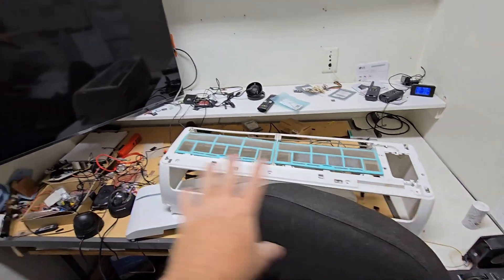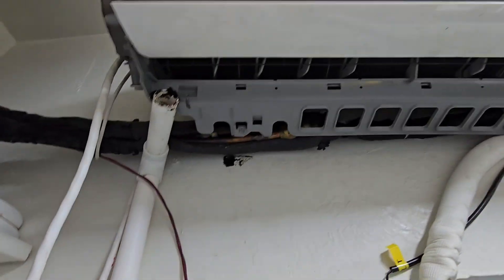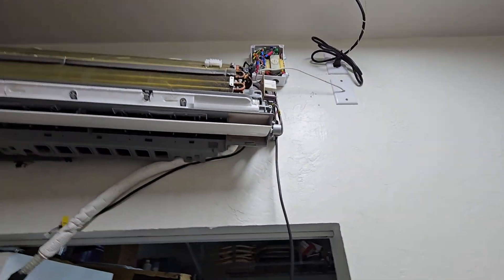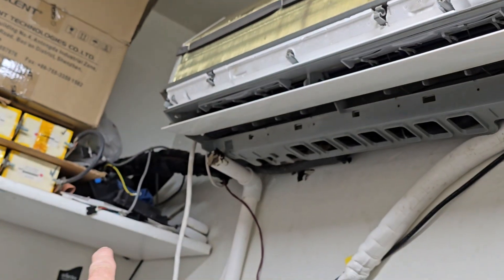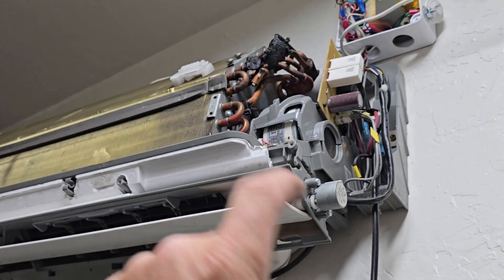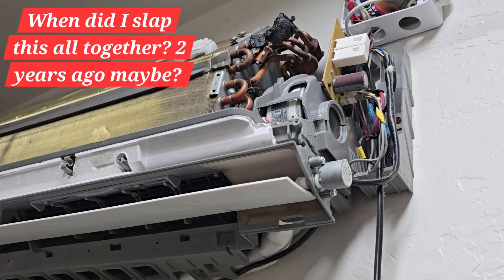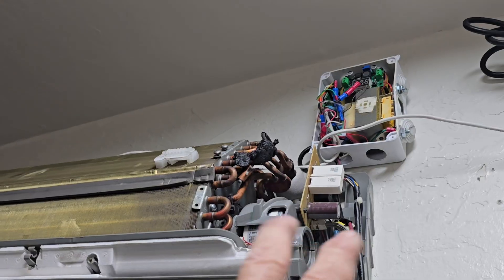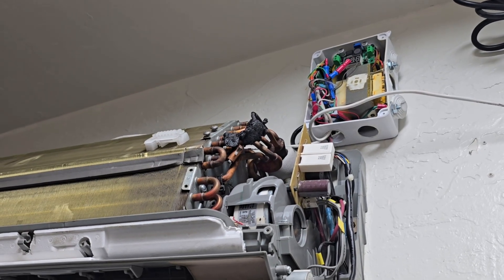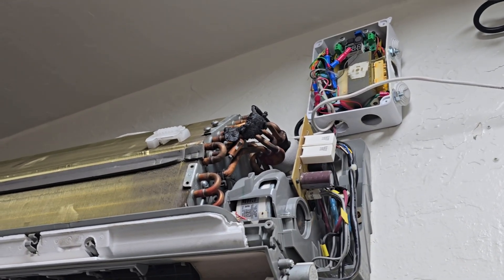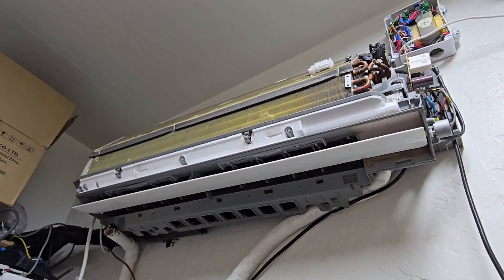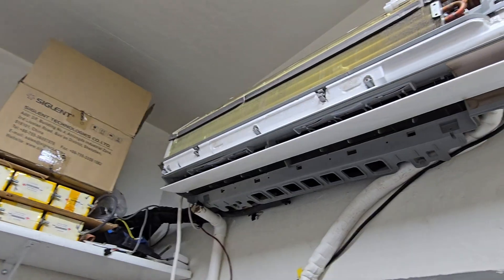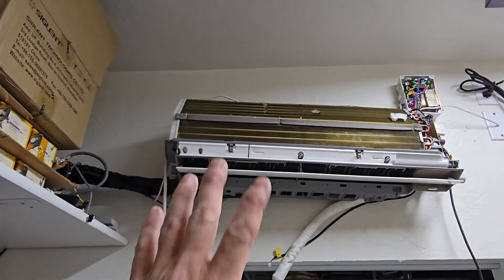I'm in here taking all this apart, got all the plastics off, gotten it partially off the wall to get into the line sets to undo the flares. Over here is a voltage doubler board I put in there. The original circuit board is just laying over there. That's a voltage doubler, just takes 115 and then outputs 300 volts DC right into the ECM motor. I'm using just a microprocessor stashed in there, programmed so I can send like a one to six volt DC signal to the ECM to basically set whatever fan speed I wanted. It just ran constantly whenever the thermostat down here was on.